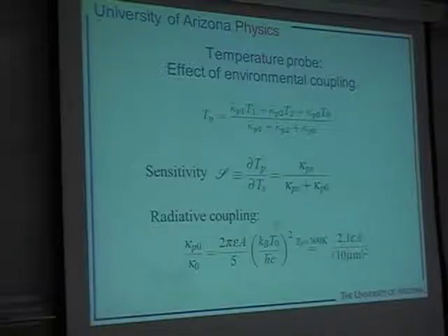It turns out you can show that the temperature of the probe, once it's reached equilibrium, is given by a simple formula: the thermal conductance between the source and the probe times the source temperature, plus the thermal conductance between the drain and the probe times the drain temperature, plus the thermal conductance between the probe and the environment times the environment temperature, all divided by the sum of those three thermal conductances.